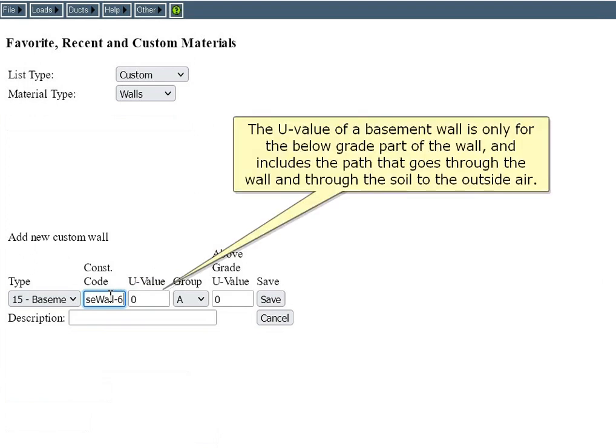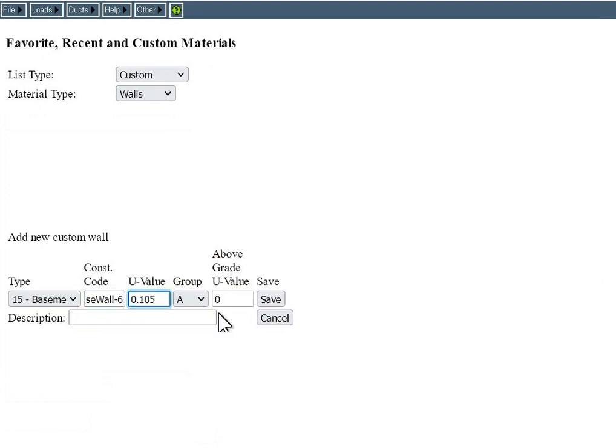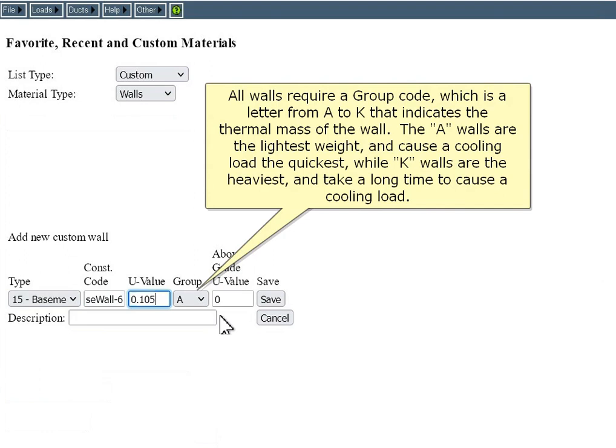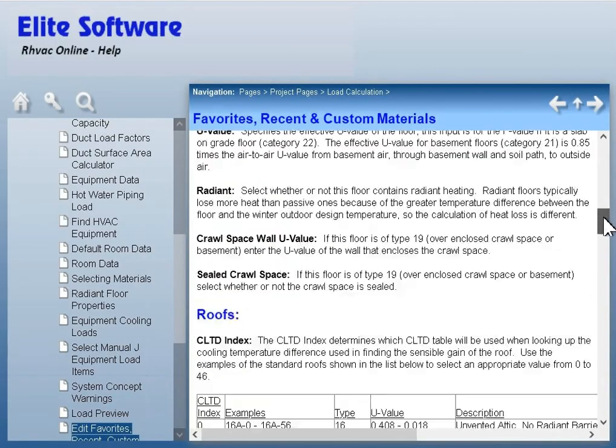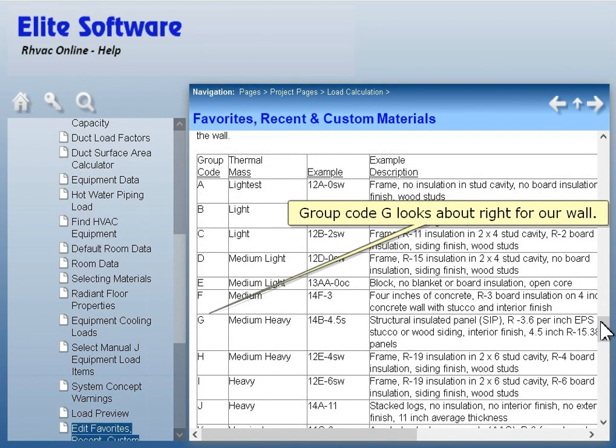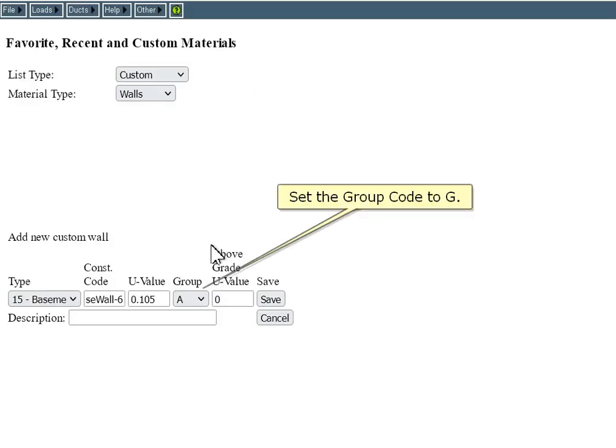The U-value of a basement wall is only for the below-grade part of the wall and includes the path through the wall and through the soil to the outside air. All walls require a group code — a letter from A to K that indicates the thermal mass of the wall. A walls are the lightest weight and cause a cooling load the quickest, while K walls are the heaviest and take a long time to cause a cooling load. Click Help on Current Page to learn more about the group input. Group code G looks about right for our wall, so set the group code to G.